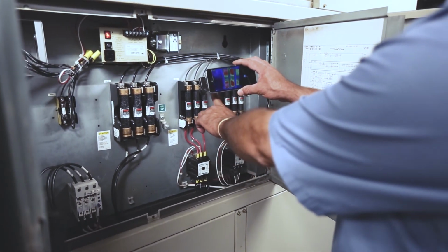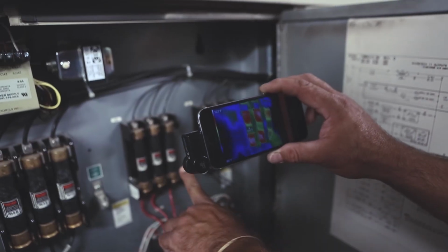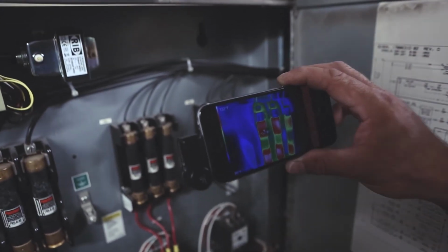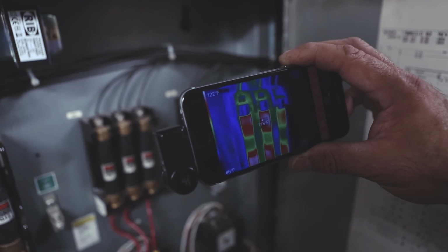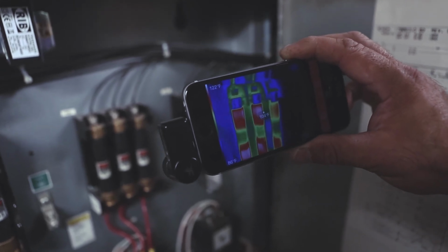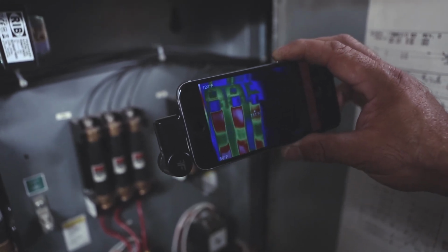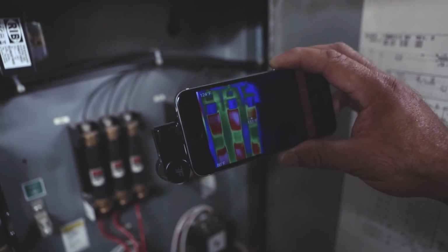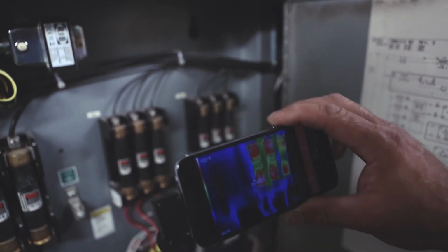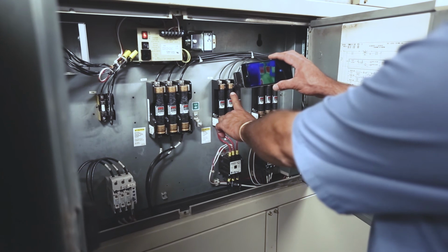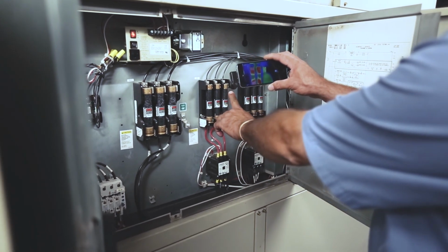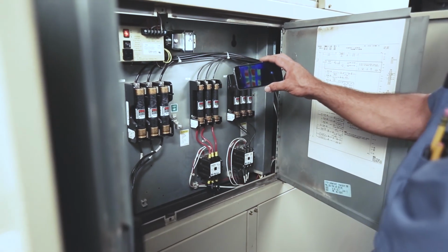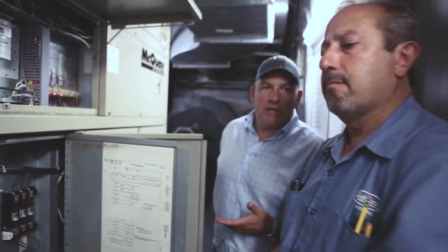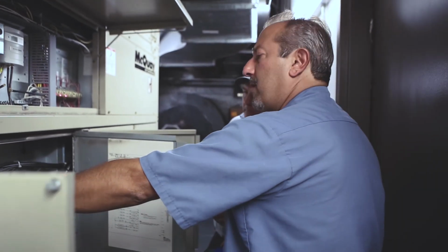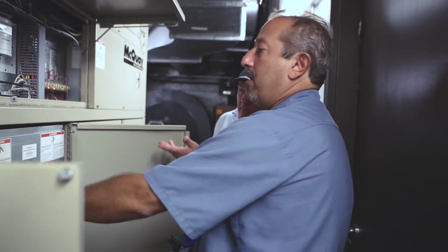You can definitely tell the difference. I have 117, I have 120, and I have 111 on the right. So you can definitely tell by the thermals that there is possibly a loose wire. If you did see a difference, maybe that's an issue, but right now you're in an acceptable range. Absolutely, it's acceptable, but again, you wouldn't know unless you put a meter on there.